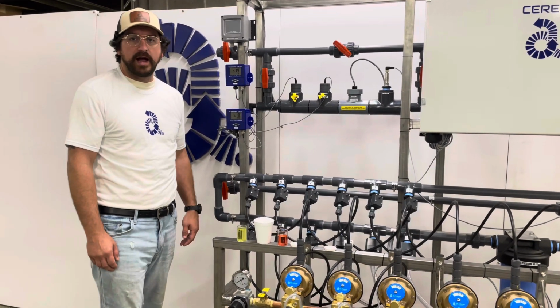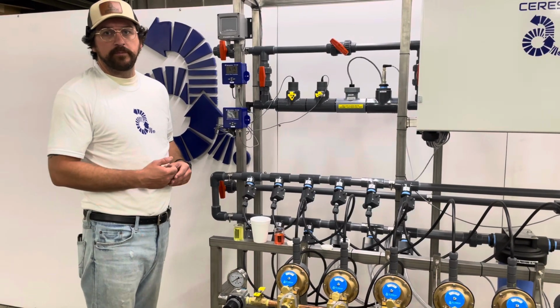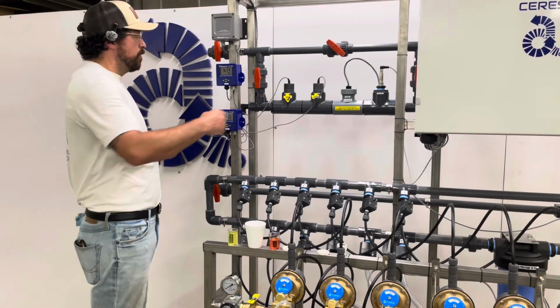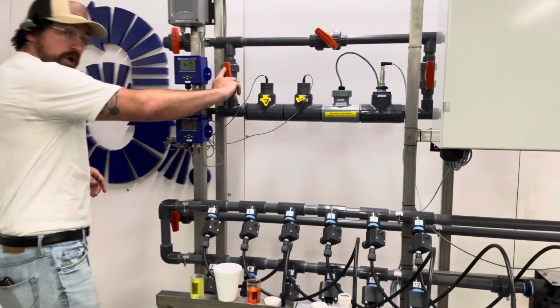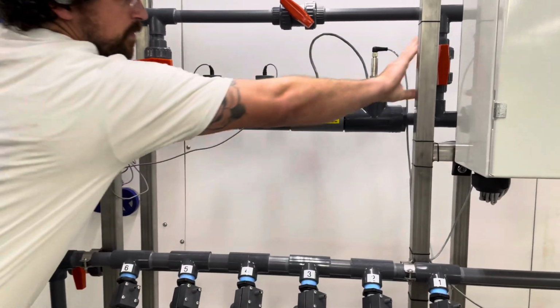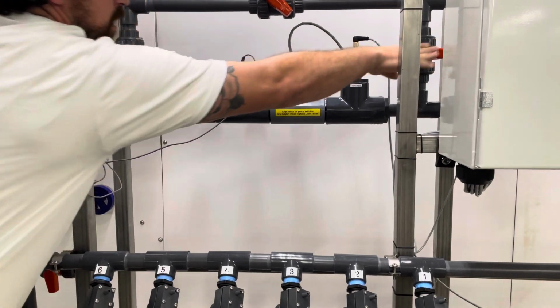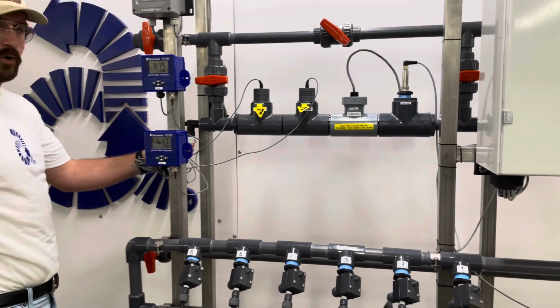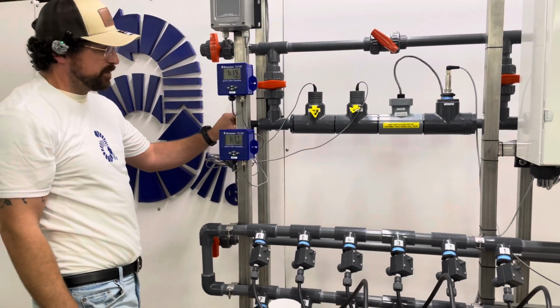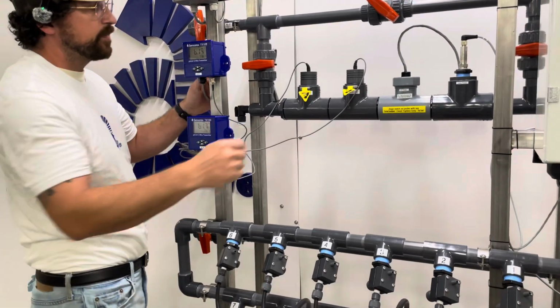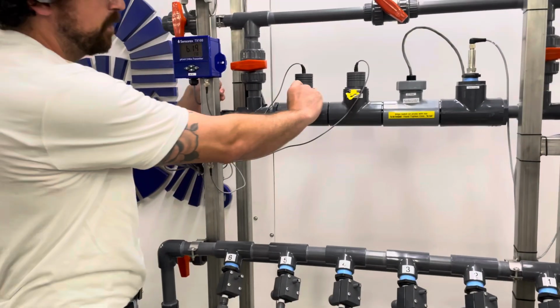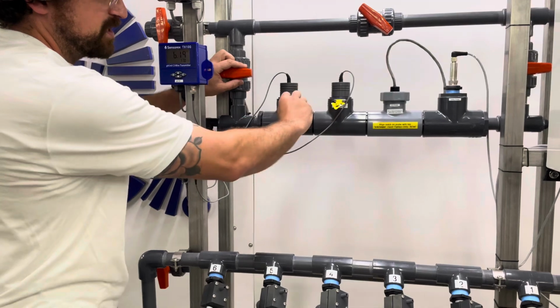Today we're going to go through how to isolate the probe loop chamber and calibrate pH probes. To start, we're going to turn the two vertical ball valves horizontal. And typically you want a bucket or something under here, but we're going to open the drain valve to relieve the pressure. We're going to calibrate probe number 2. So now that we're isolated, we can safely pull the U-pin.